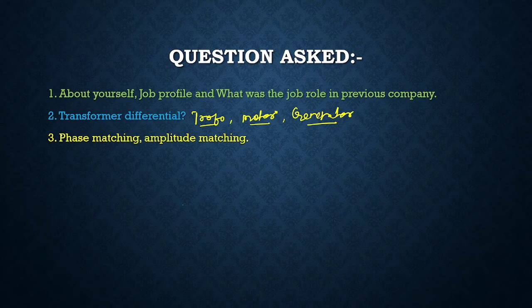Then, since phase matching and amplitude matching are part of the transformer differential, they started asking what phase matching and amplitude matching are. Whenever you discuss transformer differentials, of course there's a primary and secondary, and the CT ratio is different. Since the current ratio is different for primary and secondary, you will have a differential current. For that reason, the relay uses phase matching and amplitude matching characteristics, and accordingly the transformer differential is designed. I'm not going to describe it in detail. If you ask, I can make a video on phase matching and amplitude matching.